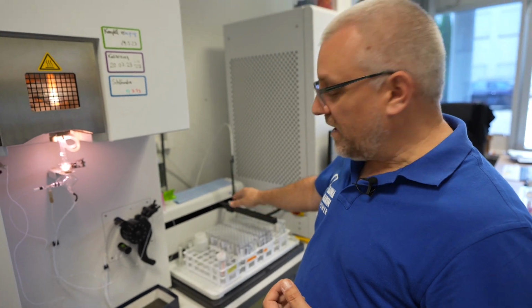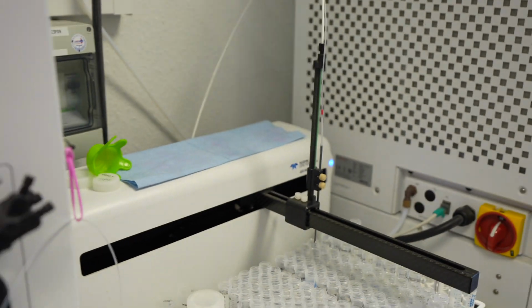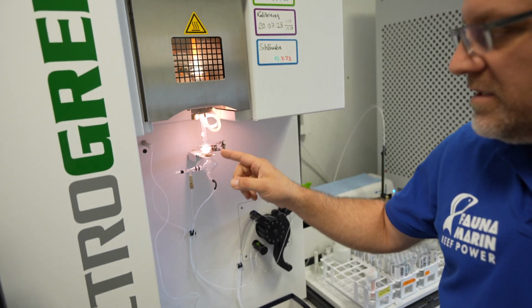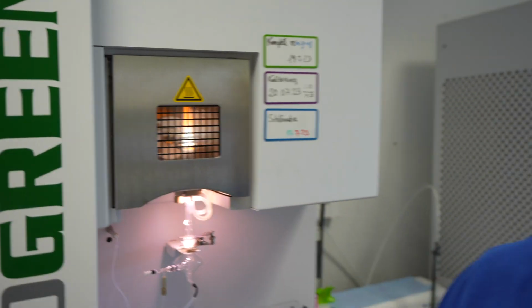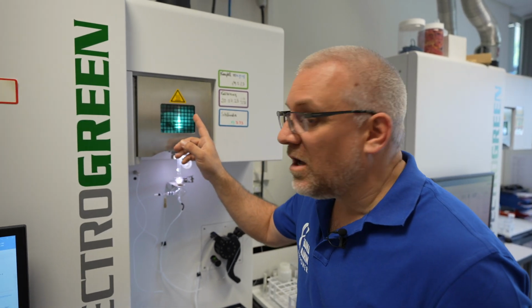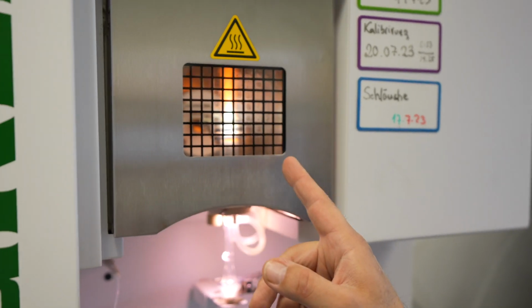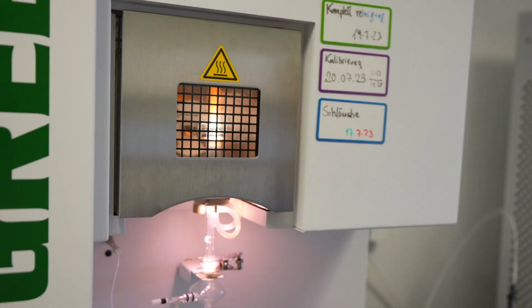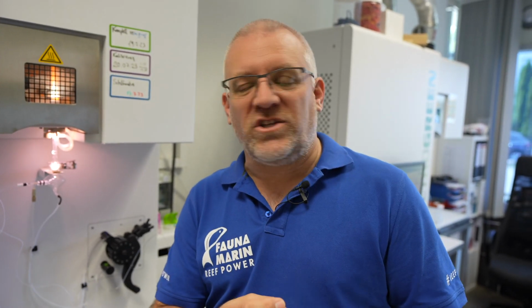To explain it easily, what we do is we take your probe, like you can see it here, it goes through the machine, it will be nebulized, and then sprayed into this flame. The metals and the nutrients inside the solution will, easily said, get a lot of energy, so they will be burned. And after they go through, now you see it changes. Now a new probe is starting. You see all the orange, and that's the sodium. That's what I mean, that every metal, every element we can detect here creates a different coloration.